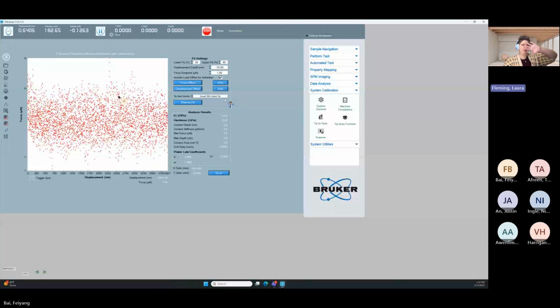So, okay, we have 5 questions. We're down 2 of them. Unfortunately for you, they're the easiest ones. Is the hardware installed? The answer is yes. The second question is, did I do my indentation axis calibration? The reason it's in this order is that the system cannot keep itself safe if it's not sensing force. There is an emergency stop installed in the probe, but if it's not sensing force, it can't work, right? So it's a sanity check of that too. We did our indentation axis calibration, which meant that we also checked the cal file. So those two things are done.